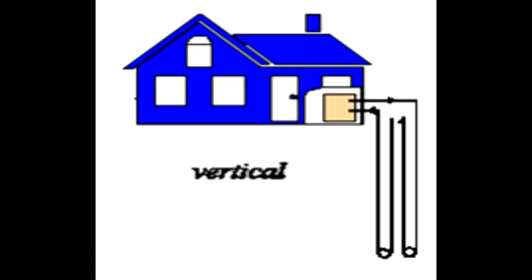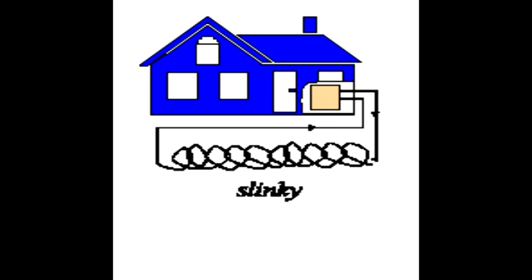It's just a matter of how much space you have. All this, at the end of the day, is a factor of how many linear feet of pipe you have in contact with the ground, and how quickly you can move heat to accomplish what you're trying to do. You also have slinky or pit loops, where we dig a big hole 8 to 12 foot deep and lay these things out in a coil configuration, then backfill that. I'll show you some other large ones we've done. That can be a lot more cost effective if you've got a lot of area to work with. It's less expensive than drilling, and especially in the Rocky Mountains, drilling conditions are always not very favorable.